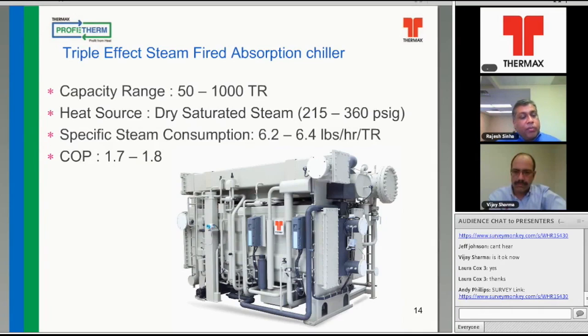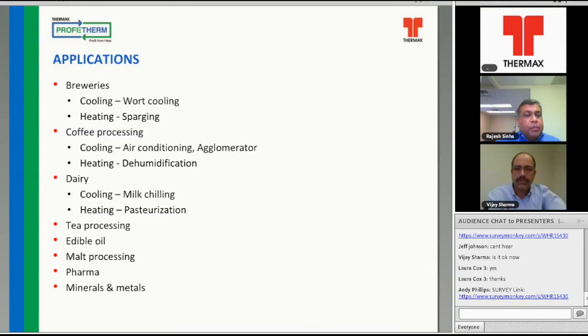The capacity range is 50 to 1,000 tons, and the heat source which could be utilized is dry saturated steam, and that would have a consumption of between 6.2 to 6.4 pounds per hour per ton, with a COP of 1.7 to 1.8. That's what the equipment looks like.